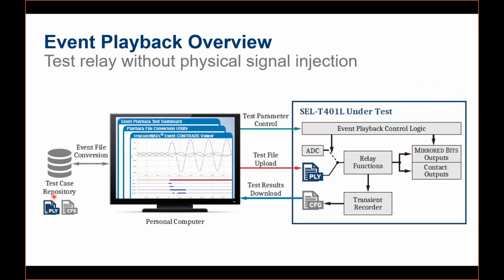because T401L is not only a phasor-based relay. It is having phasor-based technology plus traveling wave and time domain as well. So if you want to evaluate a field event that's from a relay, which is a phasor-based relay, the SEL or non-SEL relay, and you want to validate the response of traveling wave and TD-based technologies on that one. So it's a very good utility.